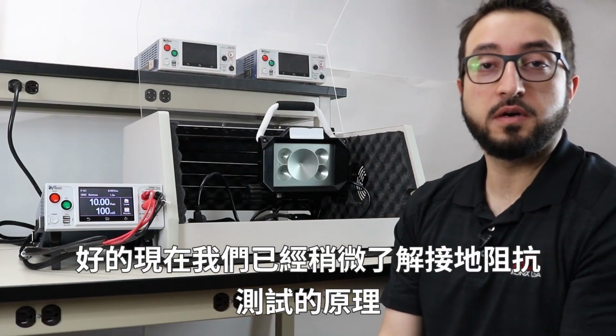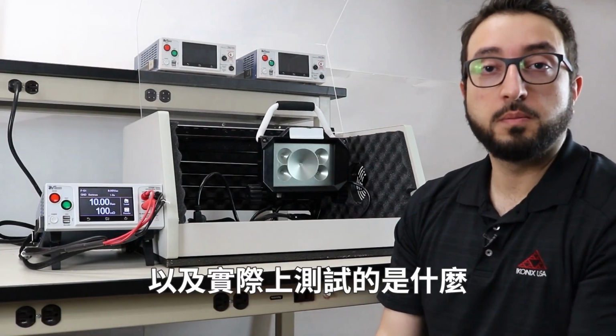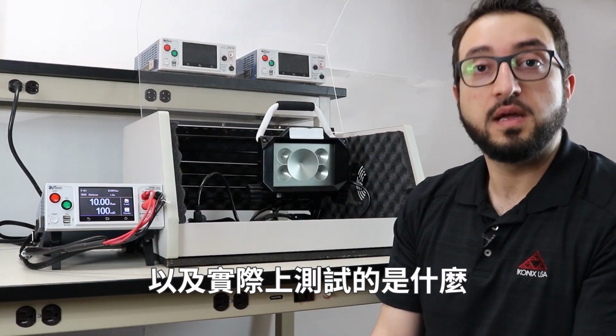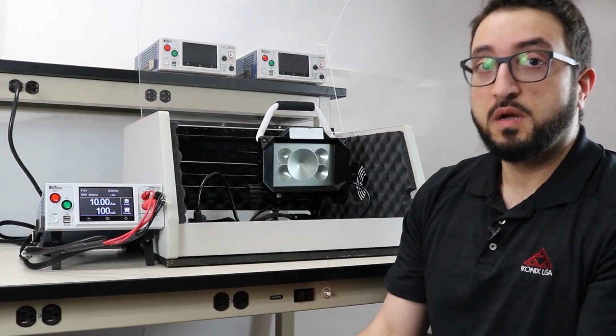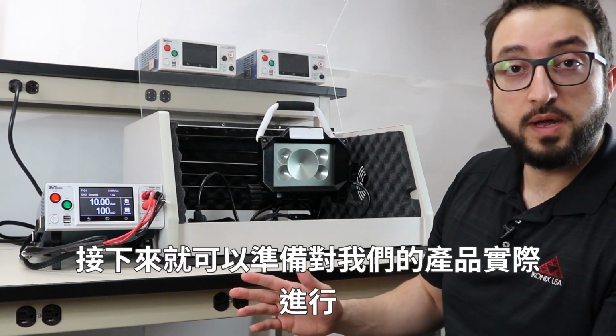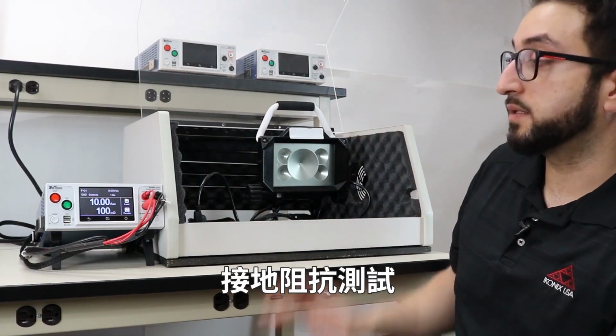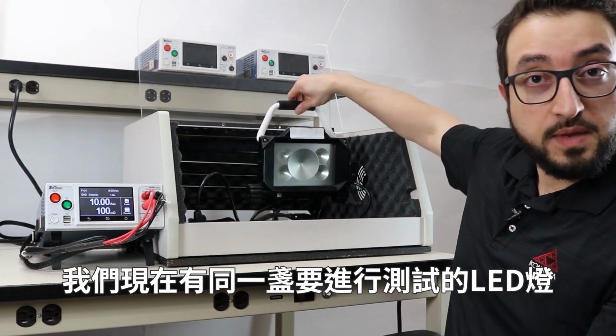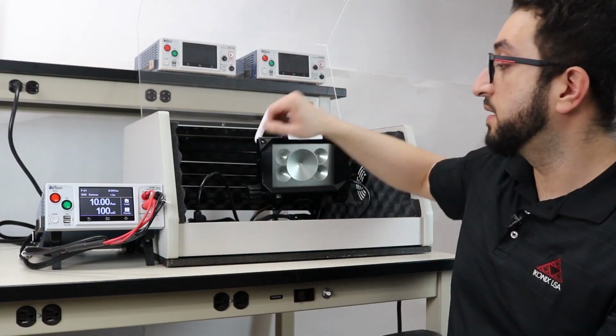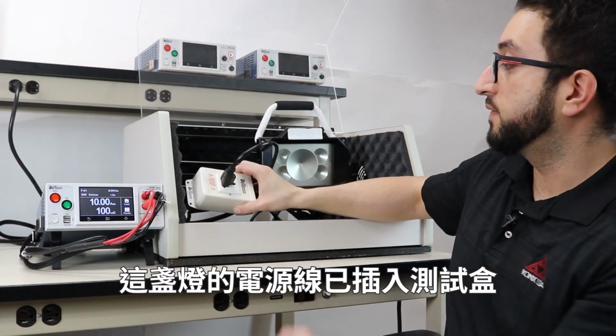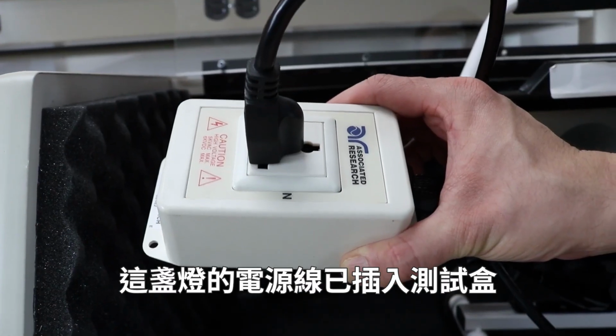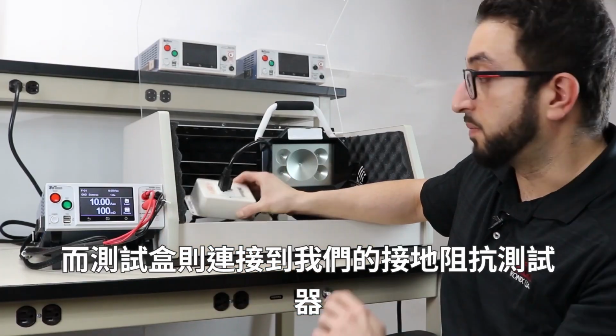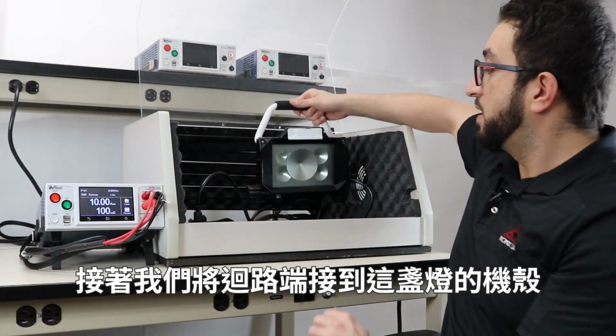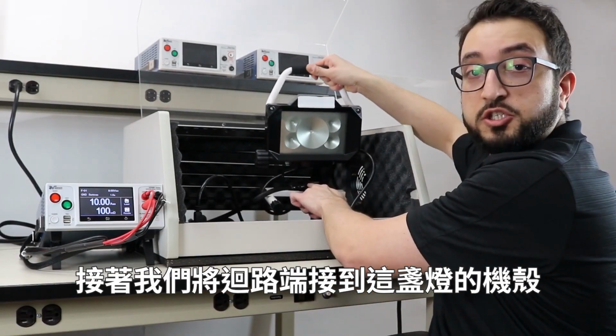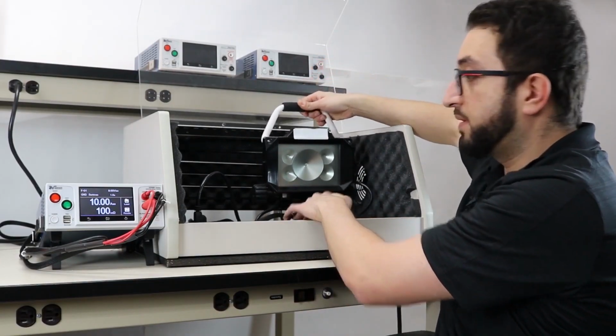Okay, so now that we've learned a little bit about what the ground bond test is all about and what is really being tested, we're now ready to actually perform a ground bond test on our product. Again, we have the same LED lamp that we're going to test. The line cord of that lamp is plugged into the adapter box, which is connected to our ground bond tester. And then we have the return connection on a chassis point of this lamp.